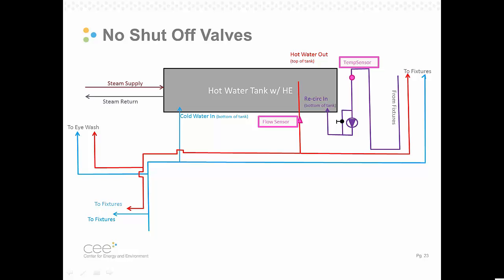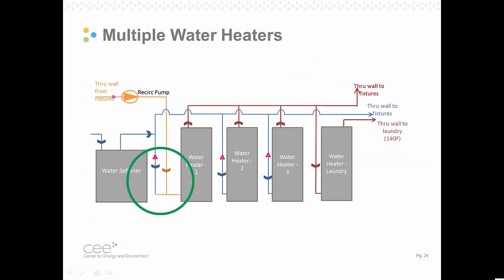The controller is able to be installed on the hot water side without much change to anything, but it's not the normal practice, so it shows the flexibility that is necessary when installing these systems. Additionally, with no shutoff valves, you have to be aware of how the system can be isolated so that cutting into the existing plumbing has the least impact on the system. That was much easier to do on the hot water side of this system because it had been replumbed more recently. Otherwise this install was pretty straightforward, but those were a couple of issues that arose and had to be handled, and flexibilities that were needed.